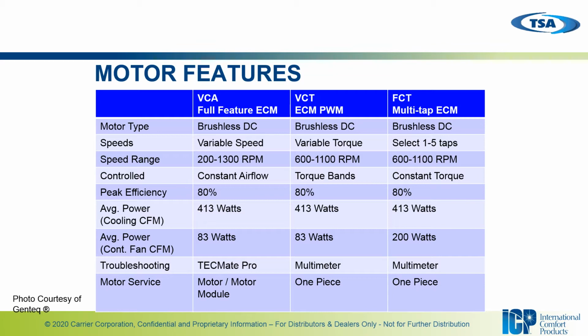The variable constant torque motor, as well, is a brushless DC motor. It has a variable torque command, so the signal going to the motor is a variable torque signal. It has a speed range of 600 to 1100 RPM and is controlled by torque bands. Peak efficiency is 80%, just like the variable constant airflow. It has the same power ratings: average power consumption in cooling, which is typically your highest speed, is 413 watts, and 83 watts in the constant fan mode. It can be troubleshot with a multimeter and is a one-piece assembly.